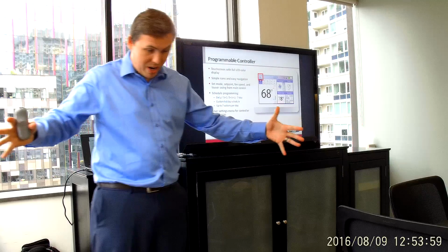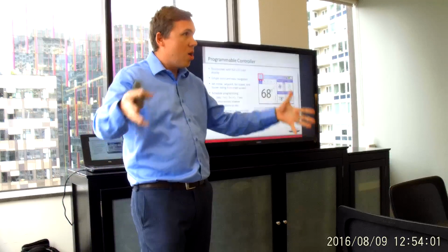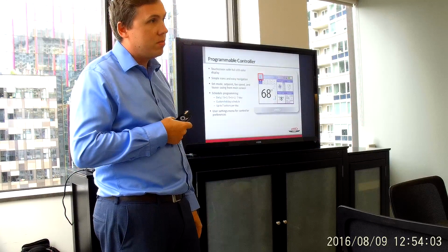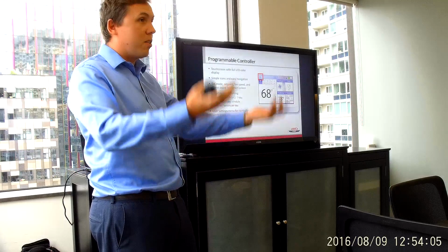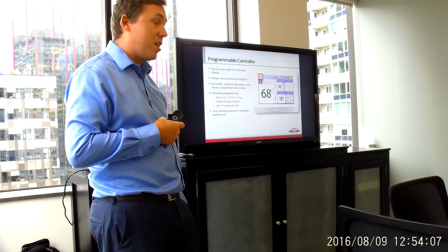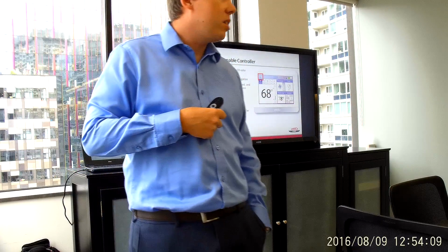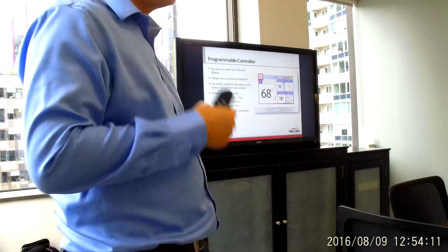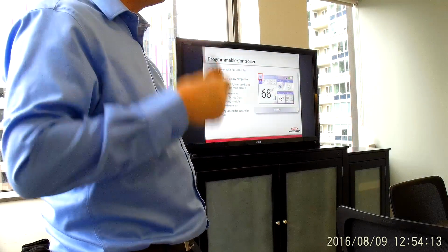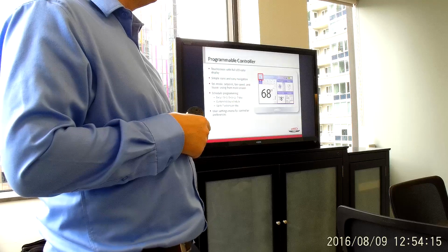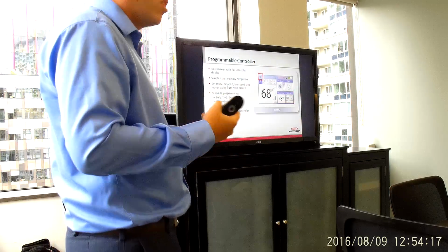I was actually on a site the other day where they put one of those massive Konica Minolta printers right underneath the wall-mounted controller. Of course, that heat's just going right into that unit. That unit's never going out of cooling. In the middle of winter, it just kept cooling because that heat was just going right into the back of that sensor. And they didn't set it back to the return air sensor. So, things like that happen, and you've got to take that into consideration.